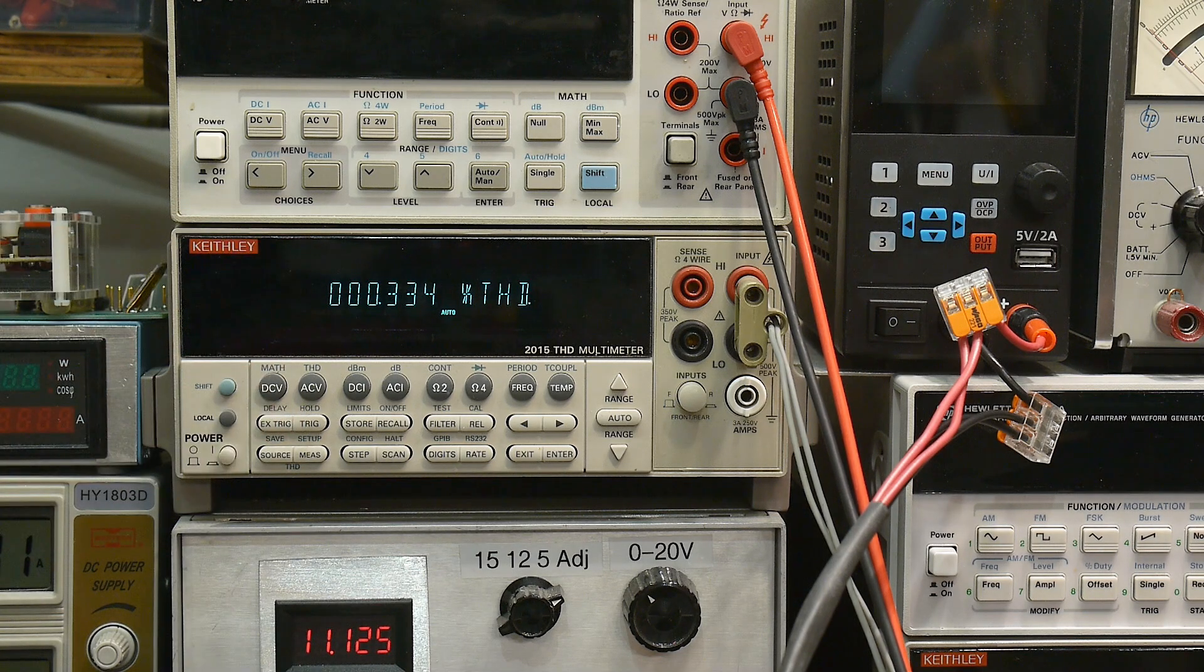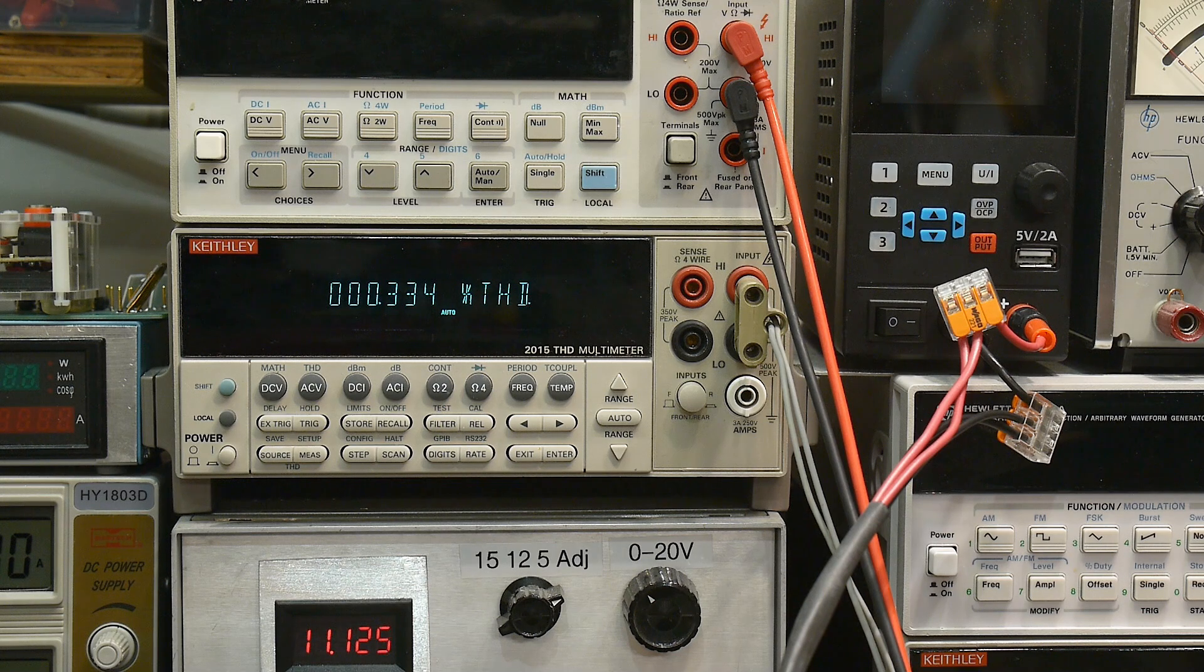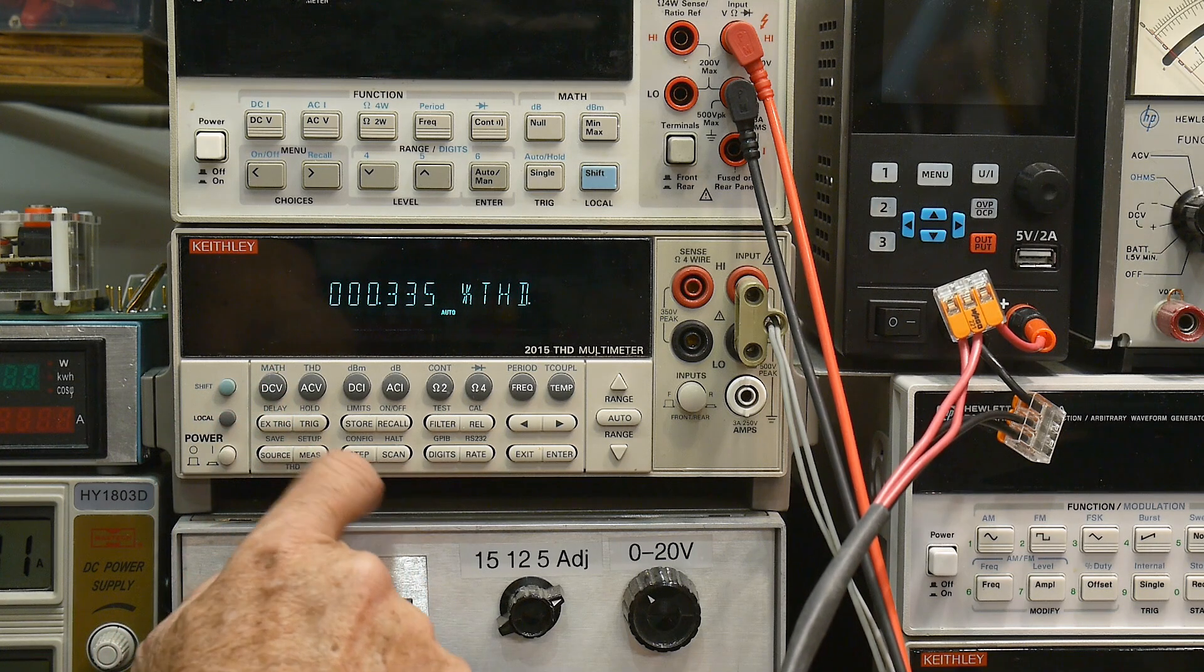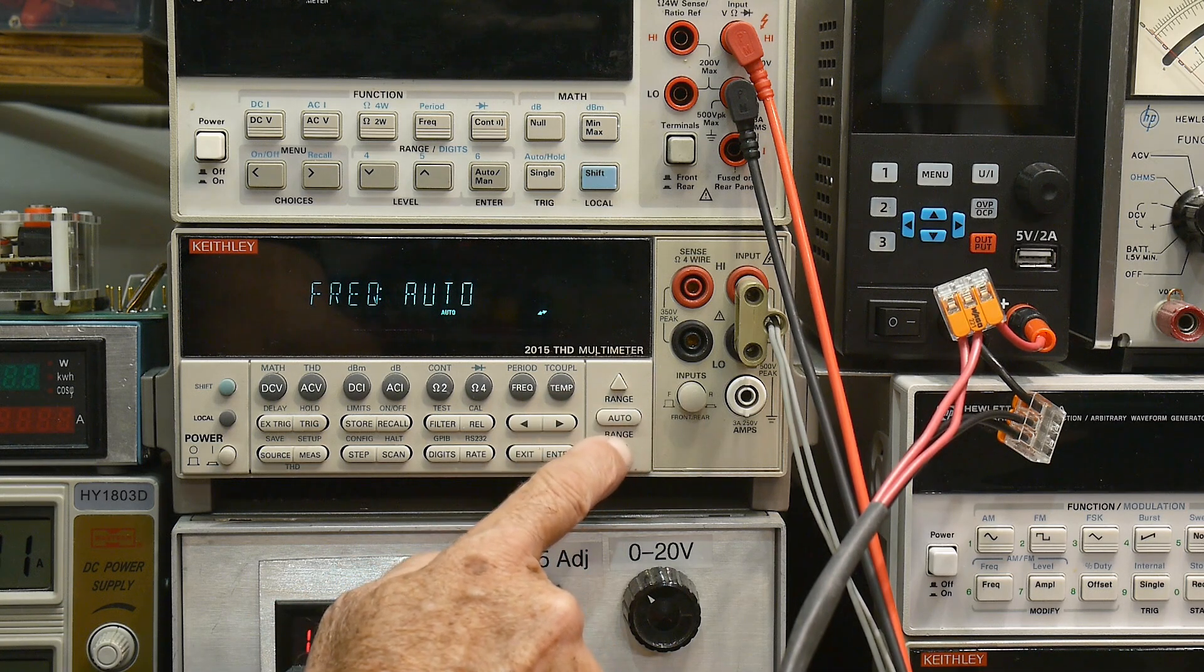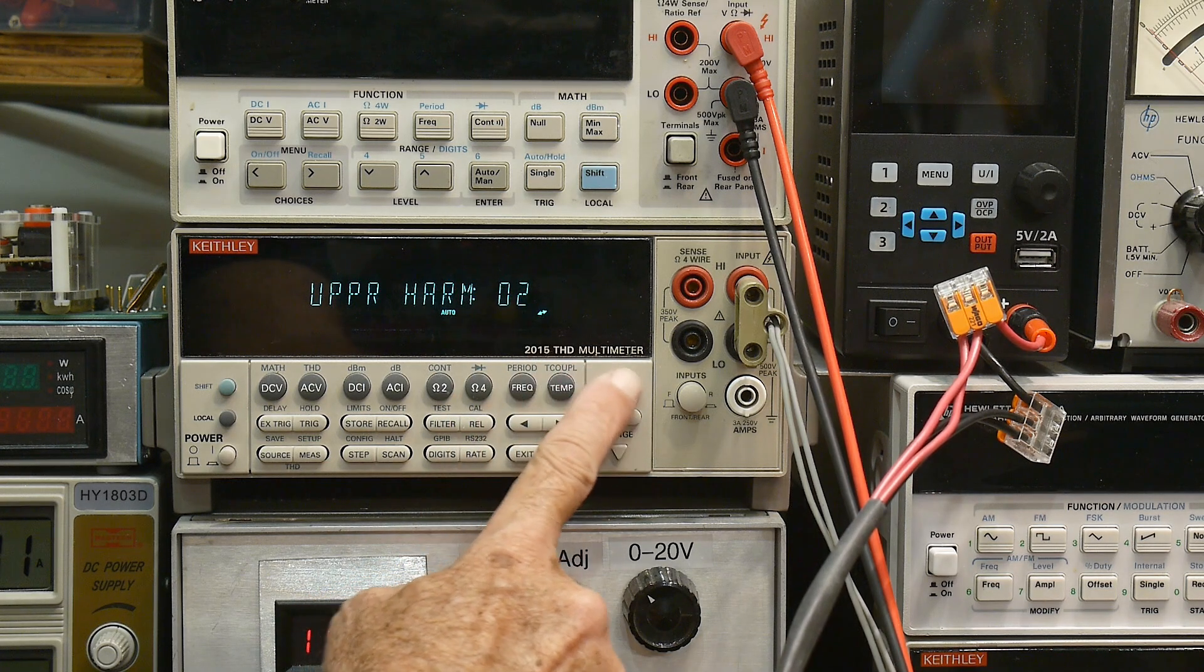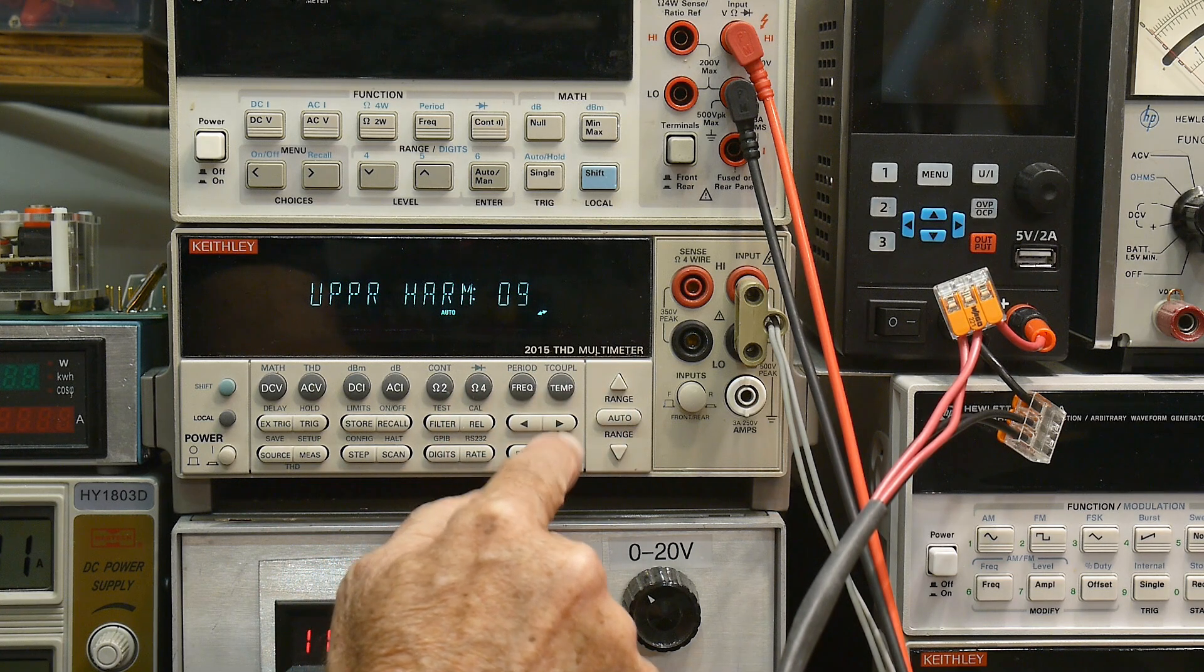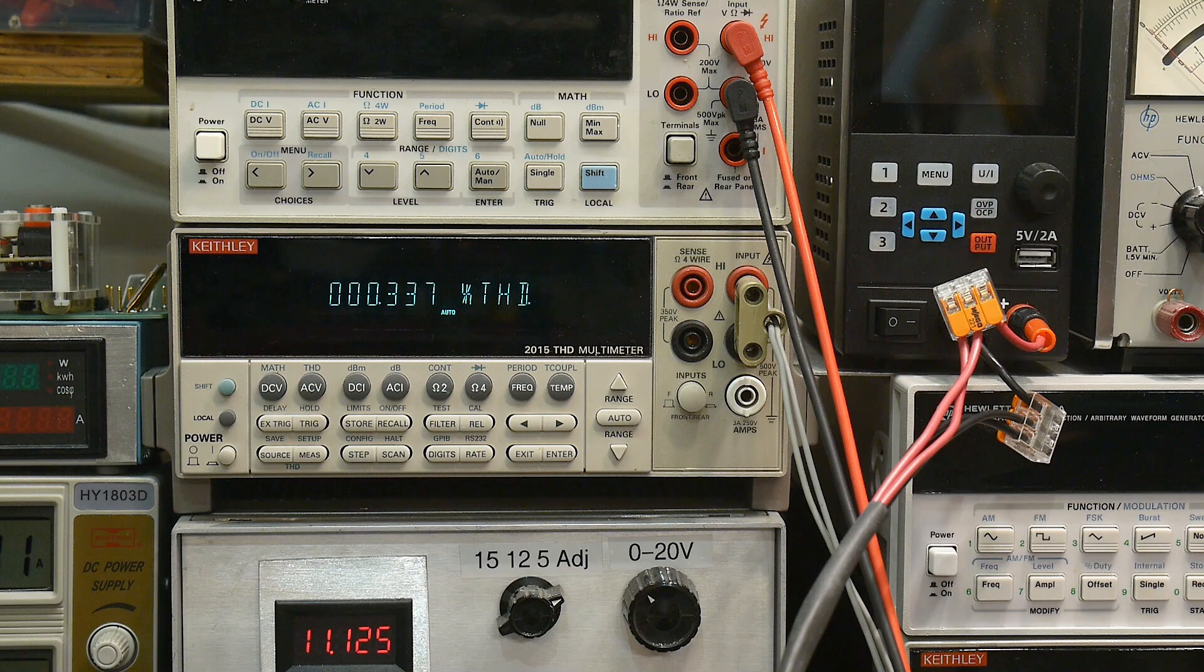Now if you own one of these Keithleys, there's something to be aware of. It can be programmed to count a certain number of harmonics and it defaults to two harmonics. If you go to measurement, total harmonic distortion, frequency automatic, it automatically detects the frequency. And then it says upper harmonics, how many do you want? I have it set to a high number now. It defaults to I think two, and I think we can go up to nine. It'll go up to nine, so let's change it to nine. So 0.3% total harmonic distortion.